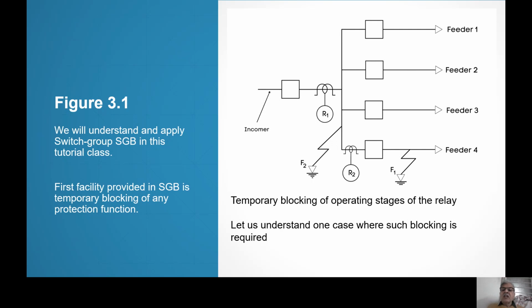And that blocking is done by SGB group, SGB1 for phase overcurrent relays. That is the I greater than feature. R1 is blocked if R2 starts. You see, what is the advantage? The very big advantage is that in earlier days, if there is a fault at F1, R2 was operating and R1 was giving backup. So if R2 operates after 0.1 second, R1 had to operate after 0.35 second.